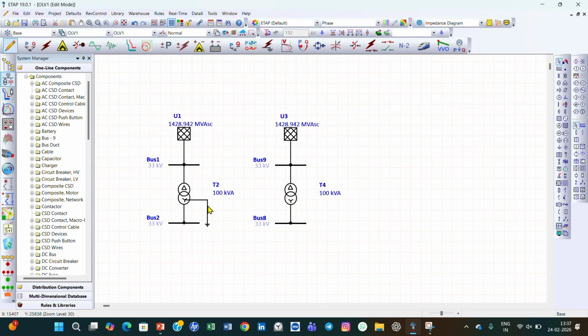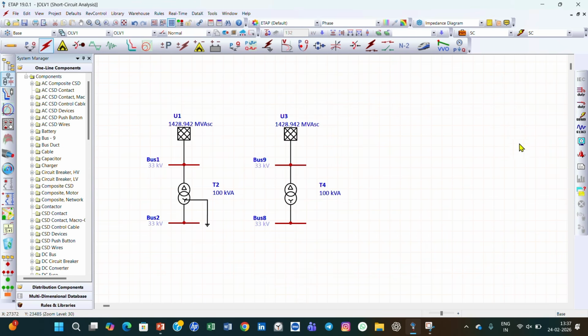I have made two simple systems to show what happens when a single line to ground fault occurs in a system when the system is ungrounded, when our system is unearthed, when the neutral is not earthed. You can see this system is grounded and this system is not grounded. Here we have the neutral grounded, here we do not have the neutral grounded. So we can simply go and perform the short circuit analysis and run IEC 60909.